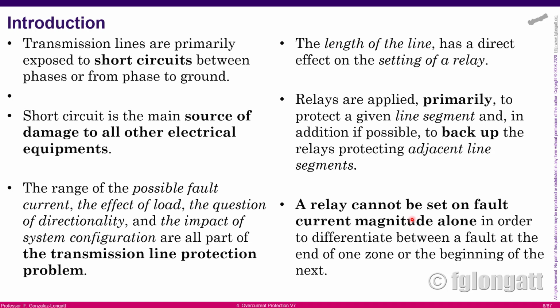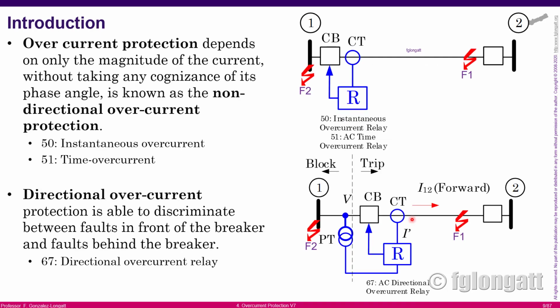Some of my colleagues from the utilities, I know they will complain to me and say that for transmission systems we mainly use distance protection. Yes, I totally agree with you, but in this case I am trying to explain to the young minds that there is a possibility that you can use overcurrent protection at transmission level. However, you must know the complexity and the problems involved, okay? I will not go against 40 years of field experience. I'm just trying to say that the brilliant young minds must understand what is happening in the field, okay?